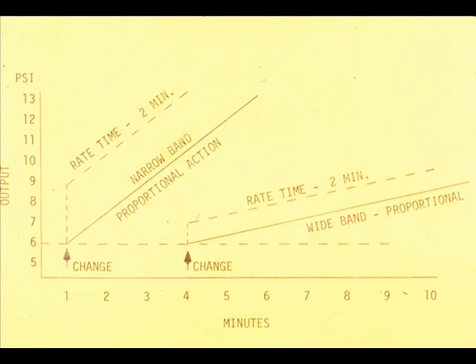Changing the percent proportional band changes the slope of the curve. For the same rate time, the controller output is advanced further for the narrow band because the output change is greater due to proportional action.